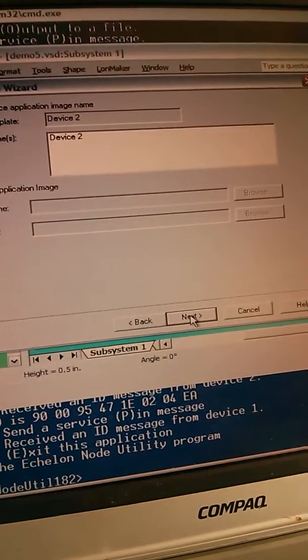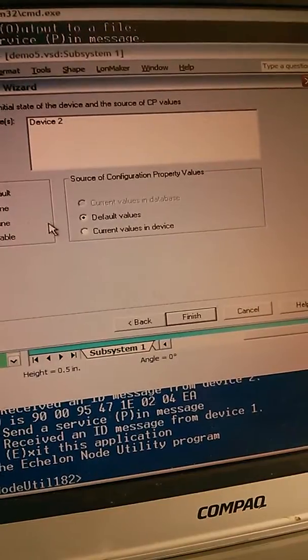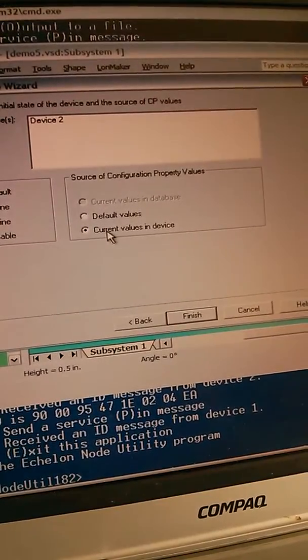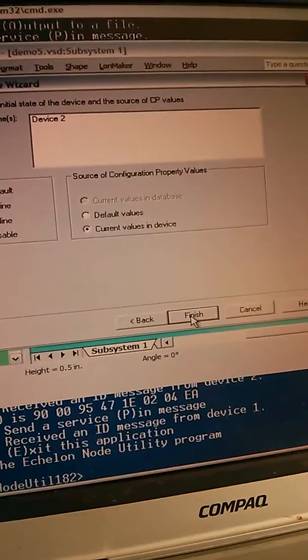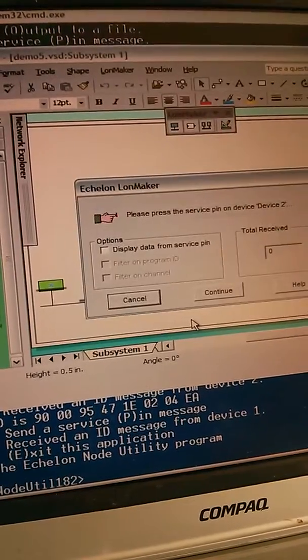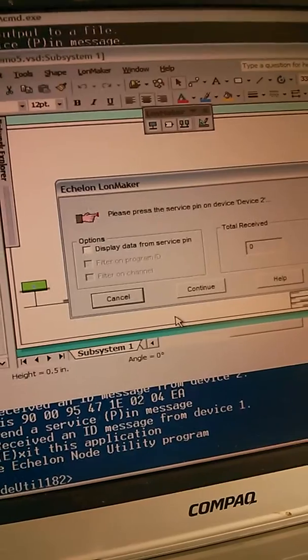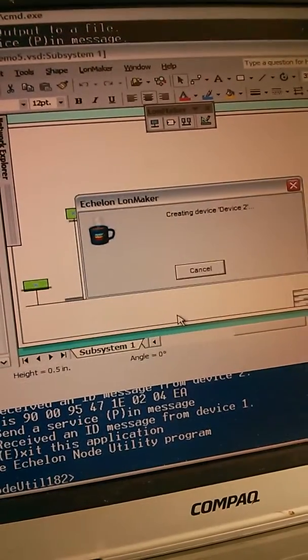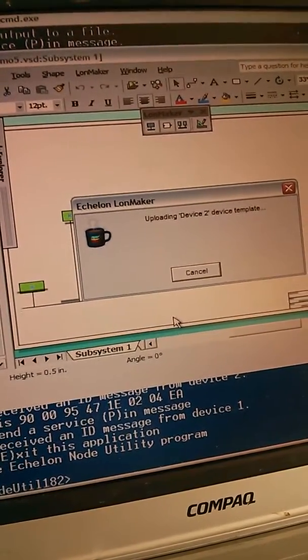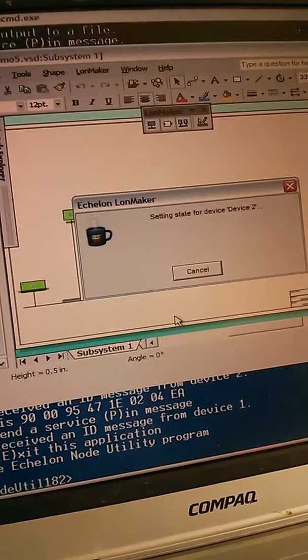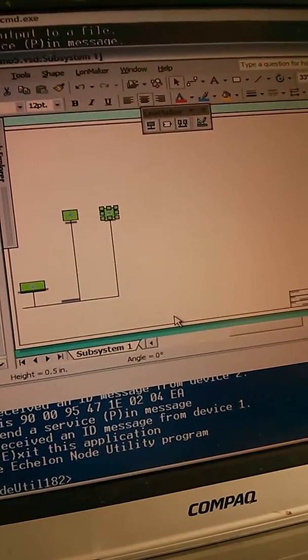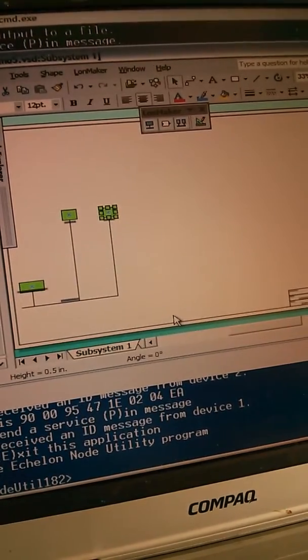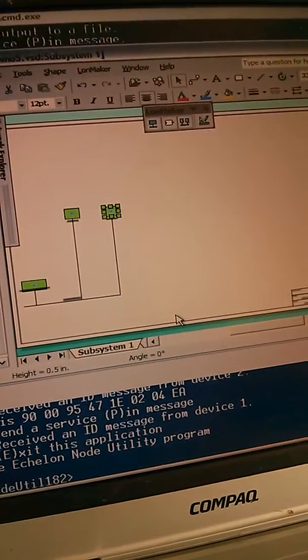So using the service pin, on my own. And it's waiting for the service pin from the second device. Got it. I put the screwdriver down the service pin hole and leant it slightly towards the LonWorks port at the top of the device so it acted like a small lever and pushed the button in.